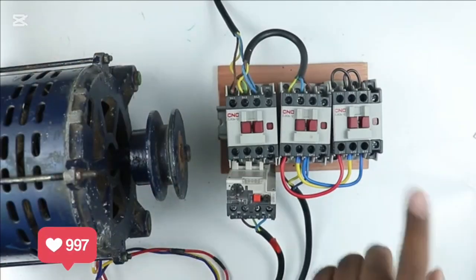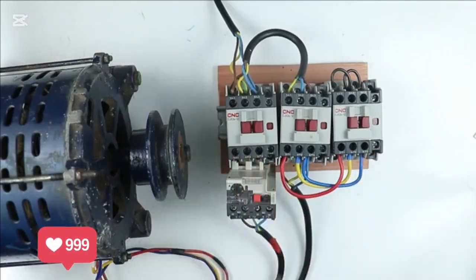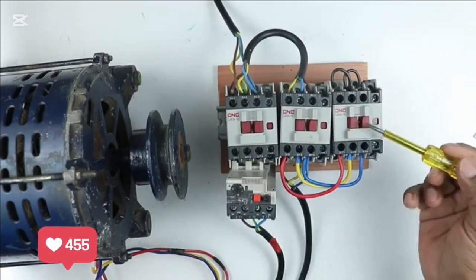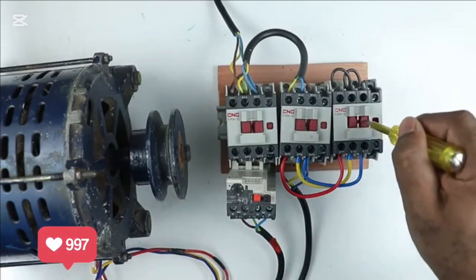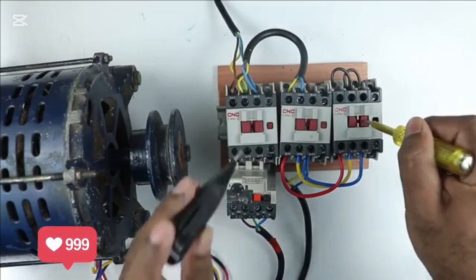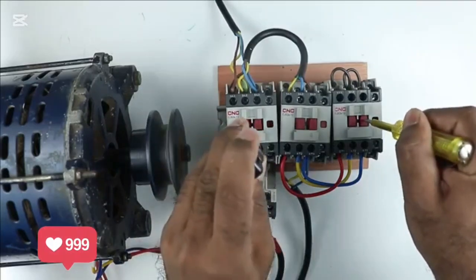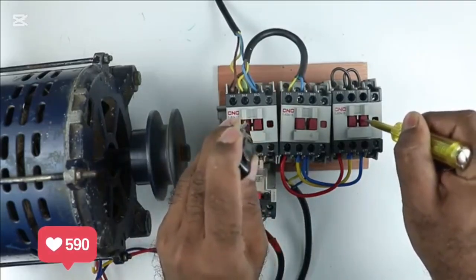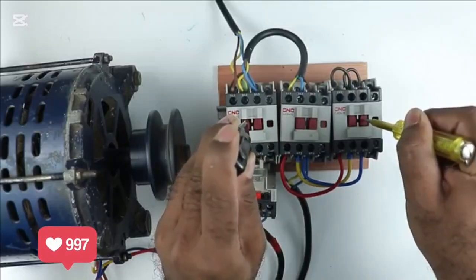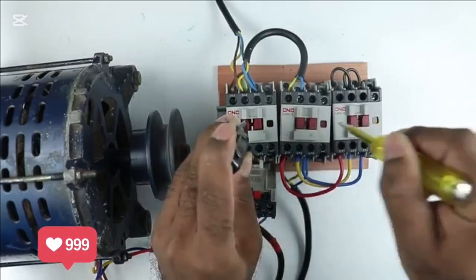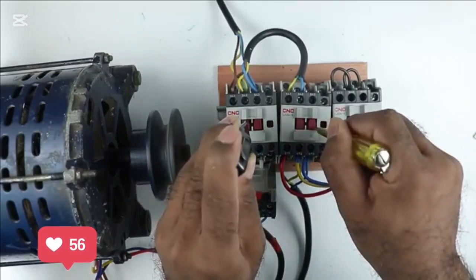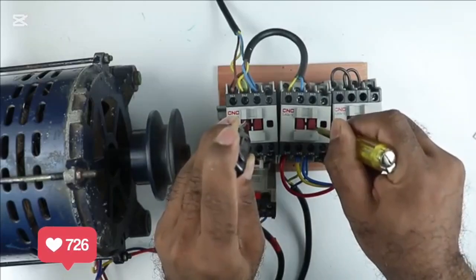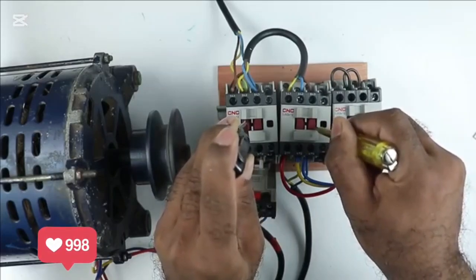If we run this motor through star delta starter, then first star contactor will turn on, after this main contactor. To start this, what I will do first is, I am turning on the star contactor. Here I turn this on. After this, turn on the main contactor. You can see motor started running. Now the timer which is connected with star delta starter, what it will do, it will turn off the star contactor and quickly turn on the delta contactor. So you can see here how instantly our motor started running in delta connection.